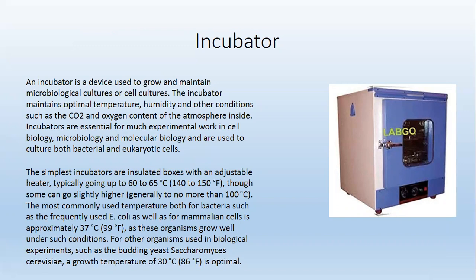Incubators are essential for much experimental work in cell biology, microbiology, and molecular biology, and are used to culture both bacterial and eukaryotic cells. The simplest incubator is an insulated box with an adjustable heater, typically going up to 60 to 65 degrees Celsius. Though some can go slightly higher, generally to no more than 100 degrees Celsius.